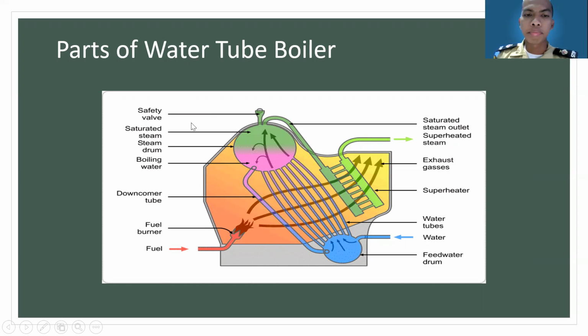And also the safety valve. The safety valve function is to release redundant force from the construction of the boilers. And also the feed check valve. In the feed check valve, the high pressure water flows along these valves, which release to the boilers and supply the water to the water tube boilers. And also the steam stop valve. The steam flow supplied outside is controlled by the steam stop valves. And also the burner. The burner is a type of device which is used to mix the air and the fuel together in the boilers at the preferred velocity. The burner is the pivotal equipment for the firing of oil or gas.